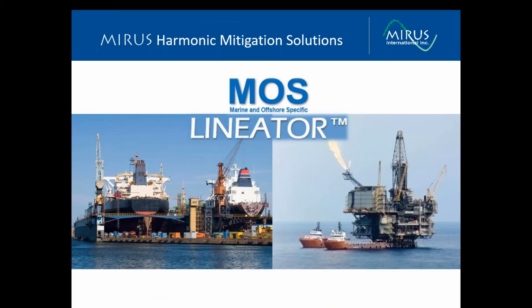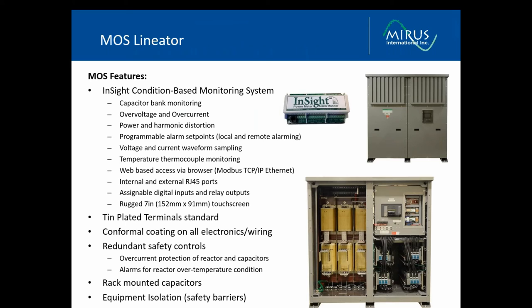So now to wrap up, I'll go through a little bit on our marine and offshore specific Lineator. This one is designed specifically for marine applications. The MOS Lineator features an advanced condition-based monitoring system that monitors the health of the harmonic filter at all times, with local and remote alarms for monitoring the capacitor bank, the reactor temperature, and the harmonic distortion or the performance of the filter. There are corrosion resistance features added on all components, and the enclosure uses marine grade paint and galvanneal steels to reduce the corrosion of the enclosure. Capacitors are isolated from the reactor, allowing for safe access.